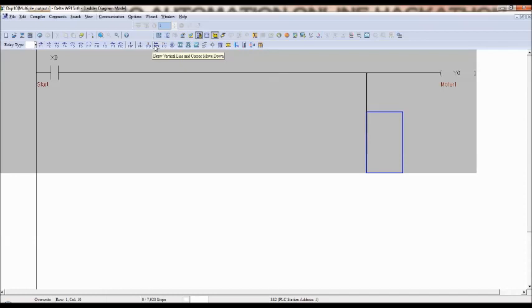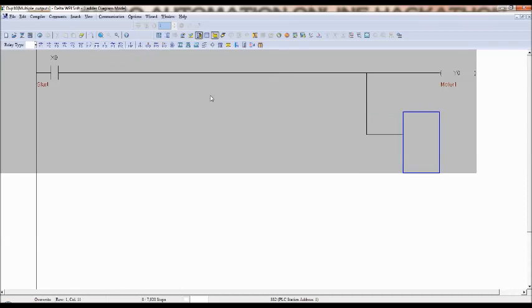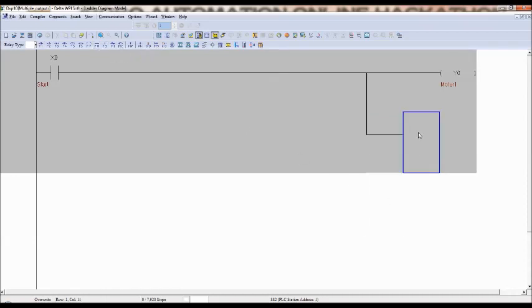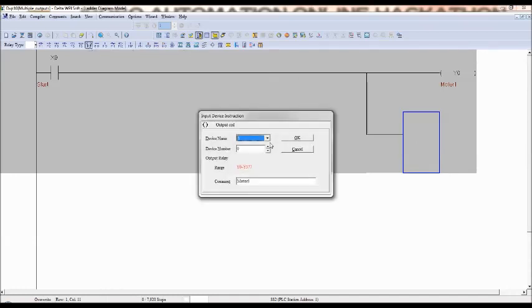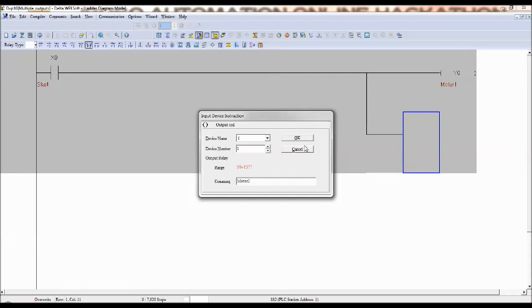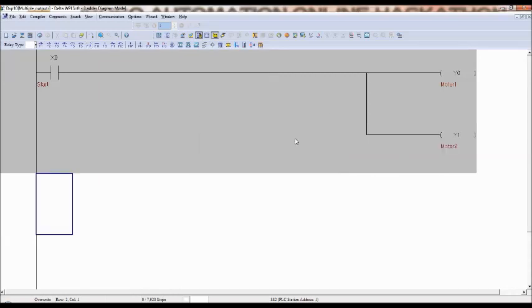And then there is a horizontal line. So first you have to draw vertical line and cursor move down option. And after that you have to draw horizontal line. So that you can take, in this place you can take one more output that is F7 again, but it's a different address that is Y1 and that you can name it as motor 2. See here, there is only one input but there are two outputs.